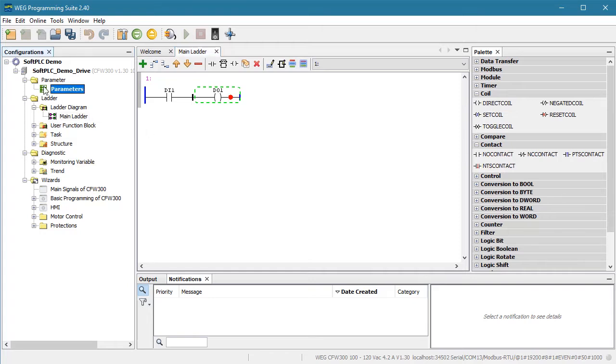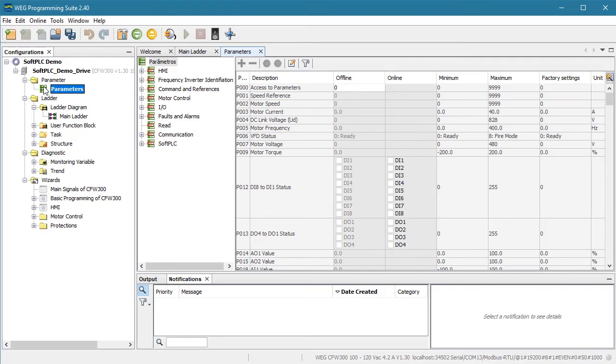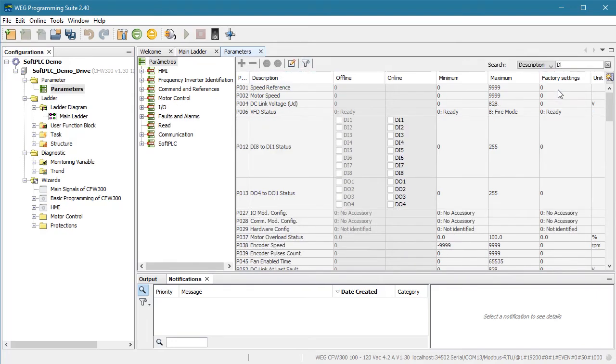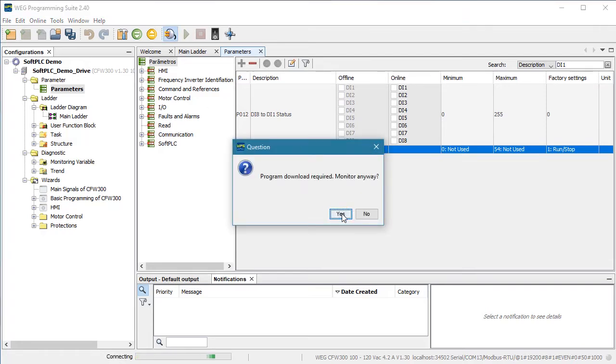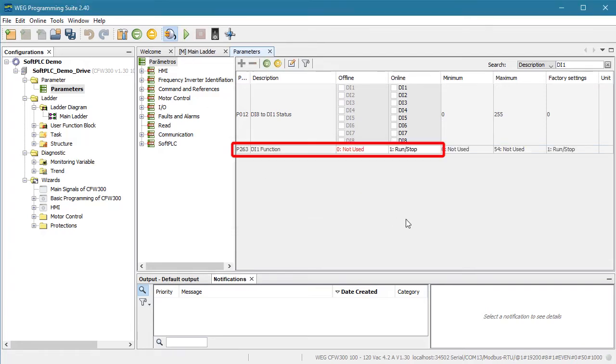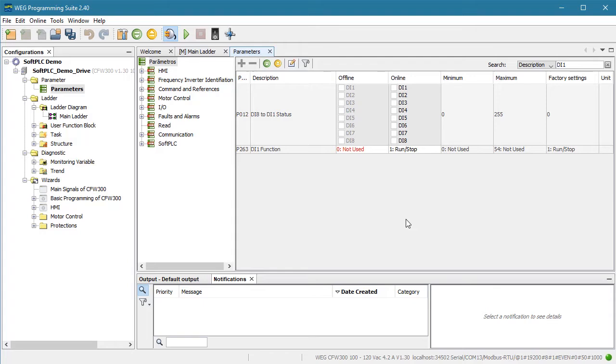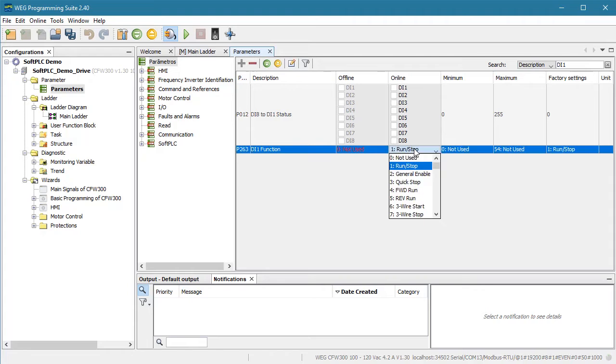Let's look at our digital input and see if we have any conflicts. If we go to our parameters and search for DI1 and we connect to the drive, we see parameter 263 tells us that DI1 is currently assigned by default as the run stop for the drive. Again, there is nothing wrong with that if you intended for DI1 to be both the manual switch input and a run stop for the drive. In fact, that's a pretty common thing to do. But since we haven't even entered our motor parameters yet, let's limit DI1 to just the Soft PLC right now and change parameter 263 to not used by the drive.